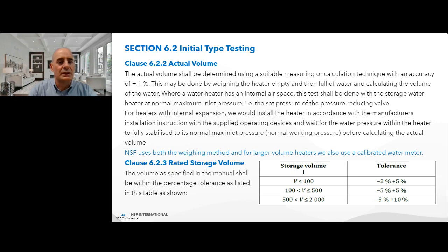Section 6.2 then covers the initial type testing. Clause 6.2.2 is actual volume. So the actual volume should be determined using a suitable measuring or calculation technique with an accuracy of plus or minus 1%. This may be done by weighing the heater empty and then full of water and calculating the volume of the water. Where a water heater has an internal airspace, this test should be done with the storage water heater at normal maximum inlet pressure. So for example, at the set pressure of the pressure reducing valve.